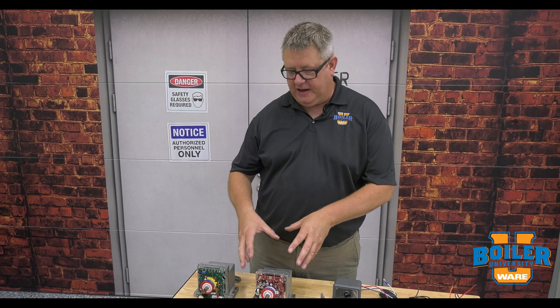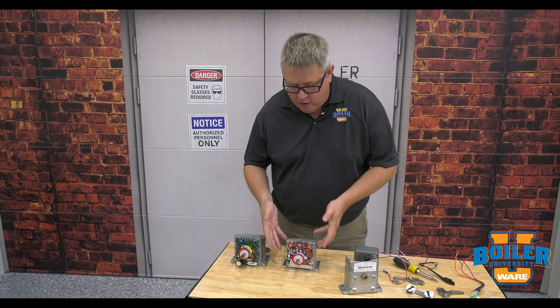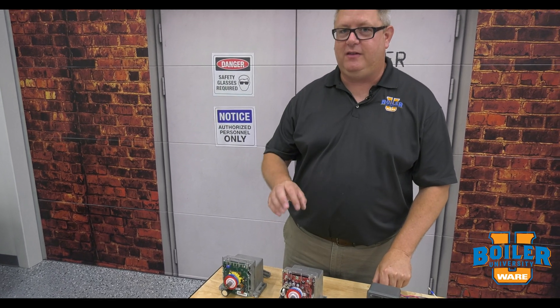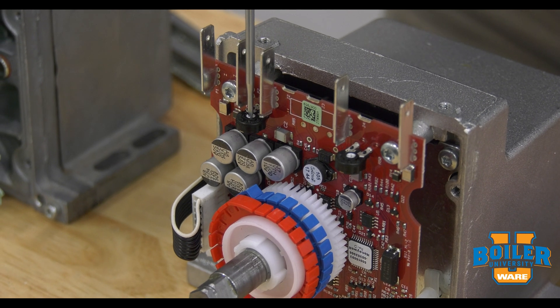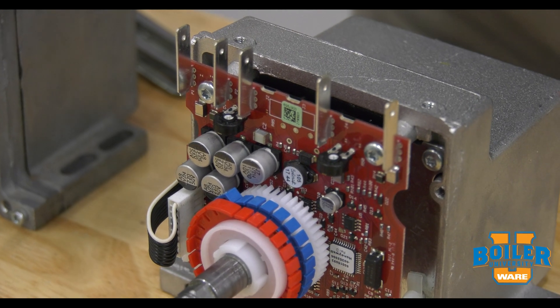On this week's Boiler Tip, we're looking at a newer style Honeywell mod motor. The first thing I noticed is there are no yellow step adjustments, but there is a second potentiometer — and that potentiometer is the key to adjusting the stroke. This potentiometer on the new mod motors can be turned fully clockwise, fully counterclockwise, or anywhere in between, giving a variation in total travel between 160 and 90 degrees.